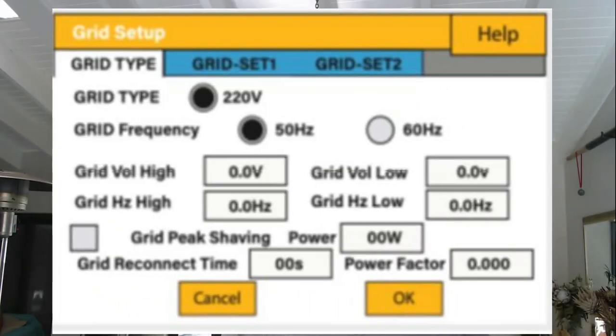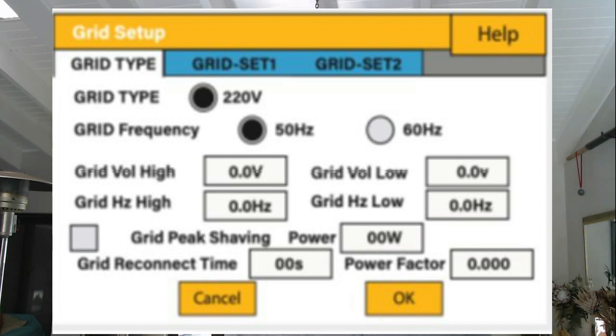On the Sunsynk, you'll find it under the Grid Setup screen — it's called Grid Peak Shaving there. You just put in your power that you want to restrict it to and click OK. Most municipalities are talking about restricting to 20 amps, which at 230 volts is about four and a half kilowatts — and that is total load, which is battery charging and your house load added together.